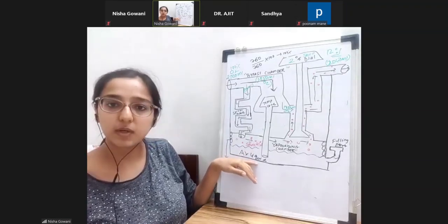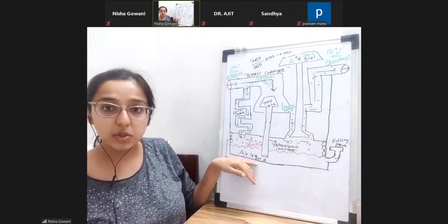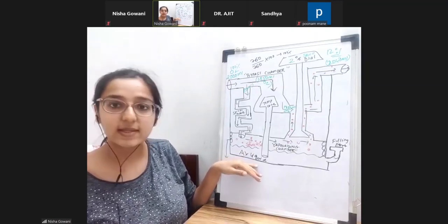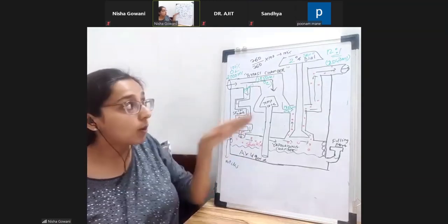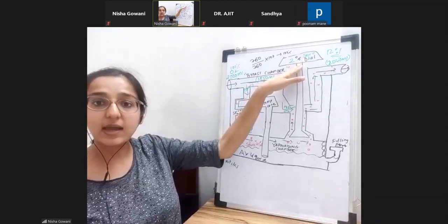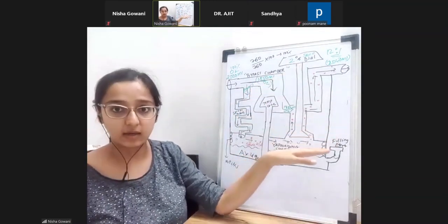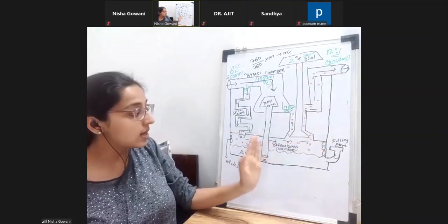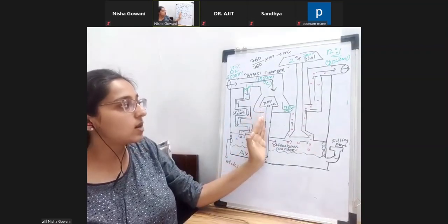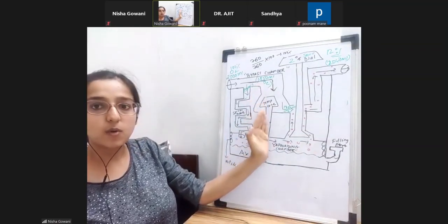When this cooling goes below 20 degrees Celsius, what's going to happen? When the liquid cools, less vapors are produced, right? So less vapors will be produced, and whatever concentration I wanted at the end, 2%, less than that might get delivered, right? Because less vapors are being produced. So what is the logical thing to happen here? This cone will rise up. This cone will move up.